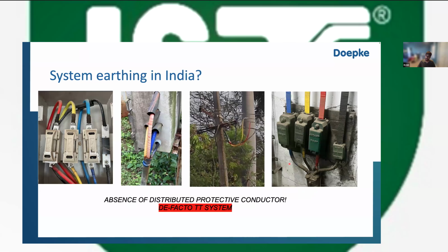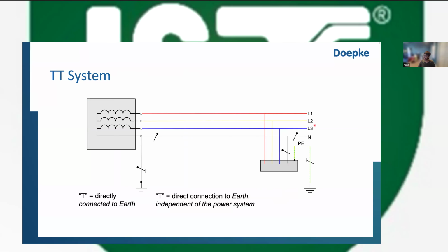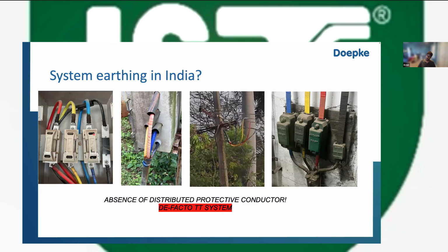If we look at what is the situation in India, so before I do that, you see this is a 4-wire system. So you are getting only 4 conductors from the DISCOM, L1, L2, L3, and N. You look at the system in India, we generally have a TT system because we are only getting a 4-wire supply, L1, L2, L3, and N. So there's an absence of a distributed protective conductor. So we essentially have a de facto TT system.